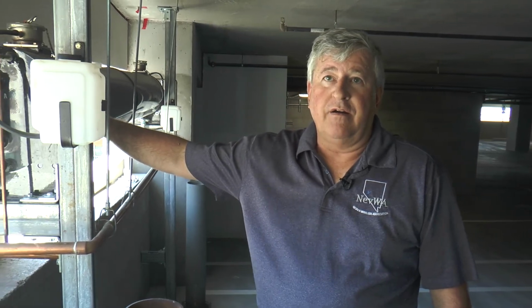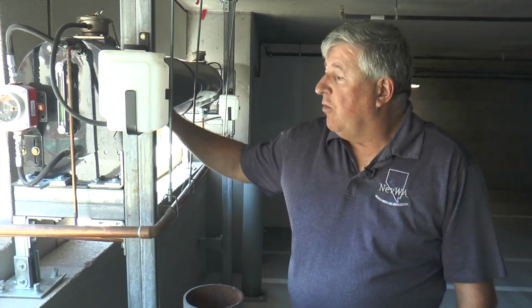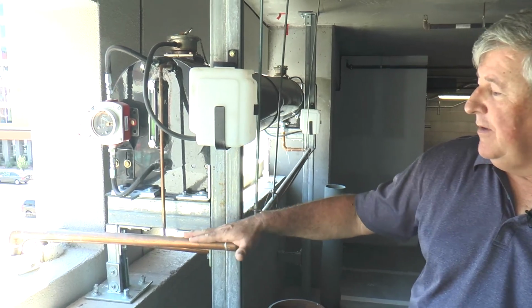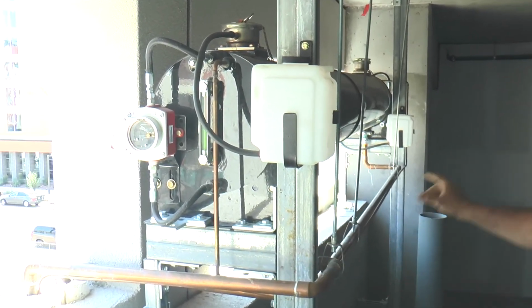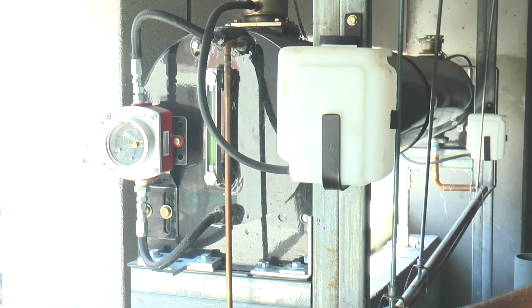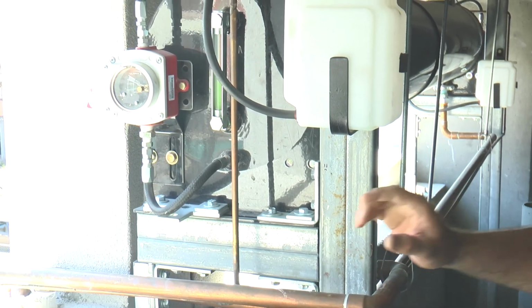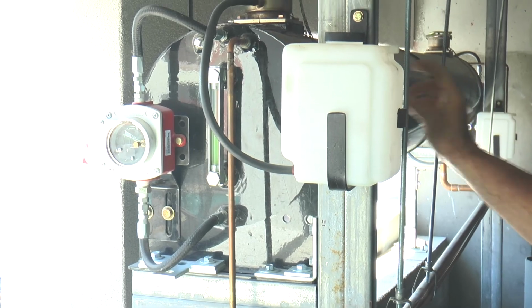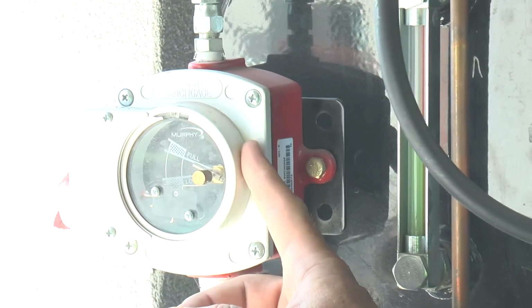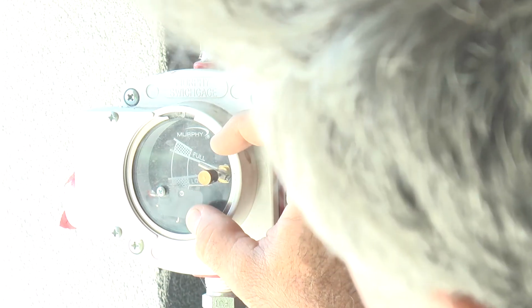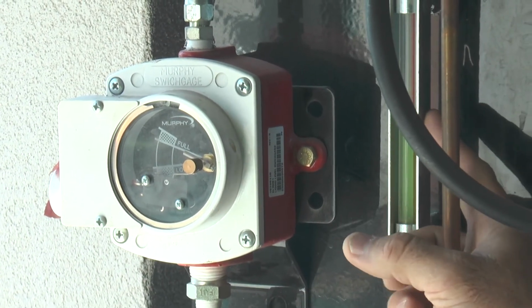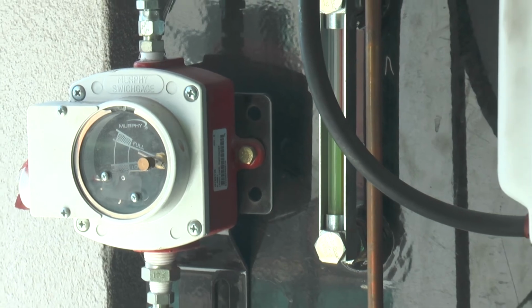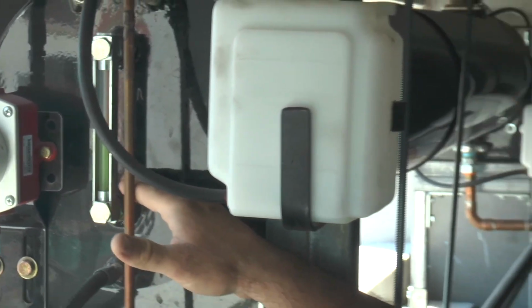We're now on the 3rd floor of the building where the surge tank is located for the generator and radiator. The surge tank is designed to provide makeup water and thermal expansion of the system. While the system is running, there's a makeup line for the jacket water and another makeup line located here for the charge air cooler circuit. Each side of the tank is split in half. Each tank is given a level gauge, so it will give you exactly where it's sitting, and then you have a sight gauge.